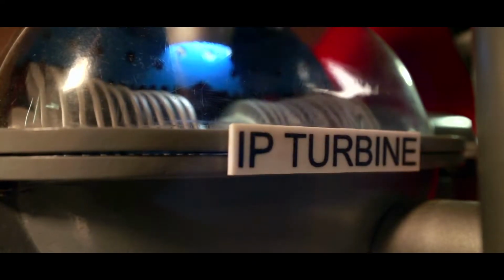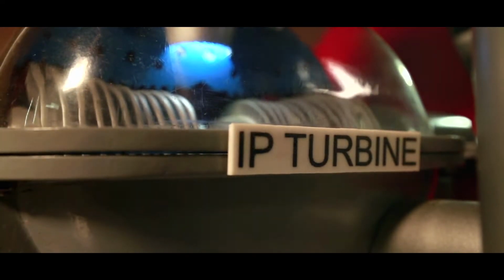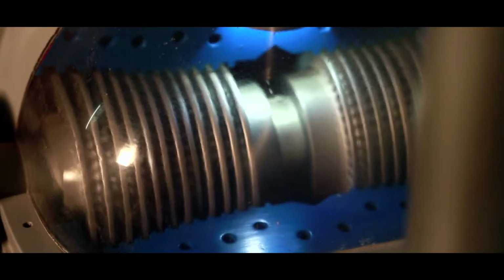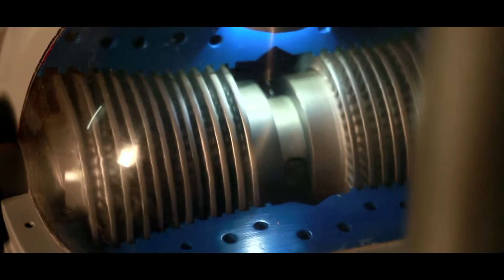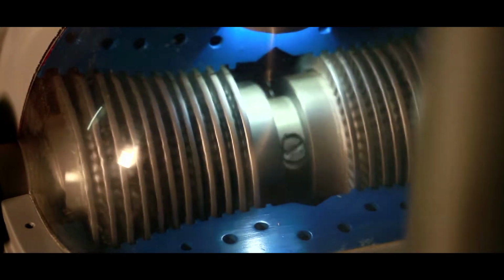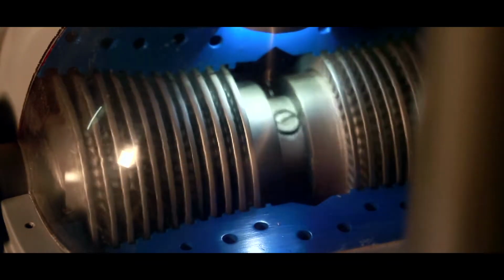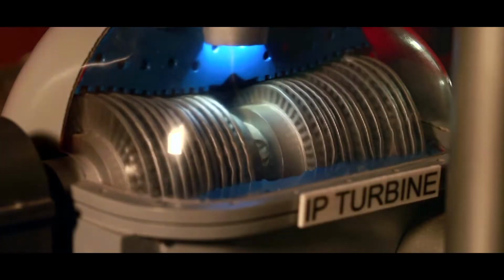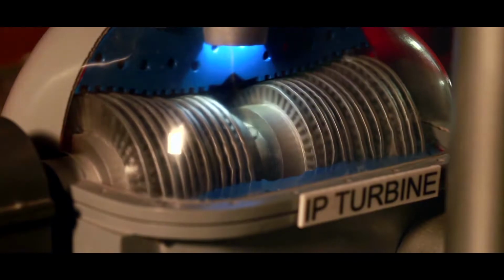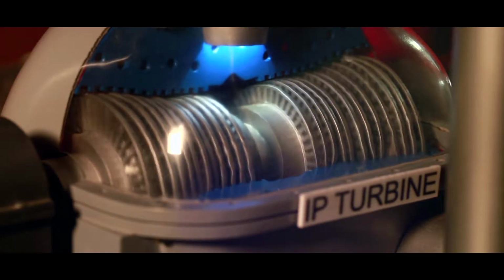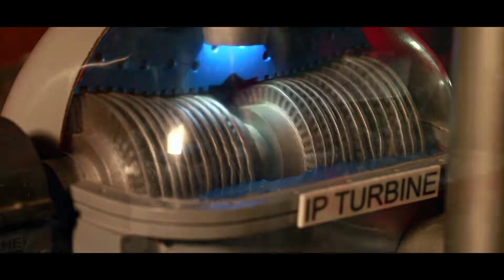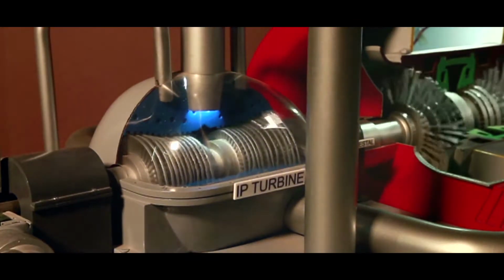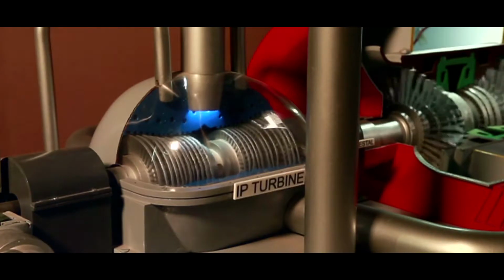Next in command is the intermediate pressure turbine, more commonly referred to as the IP turbine. While the inner casing of the IP turbine is also split like the HP turbine to accommodate thermal expansion, the similarities end there. The IP turbine is a double-flow construction turbine. Steam enters the inner casing from the top and the bottom and is split in the middle to turn the blades, which are a total of 12 blade stages on either side.